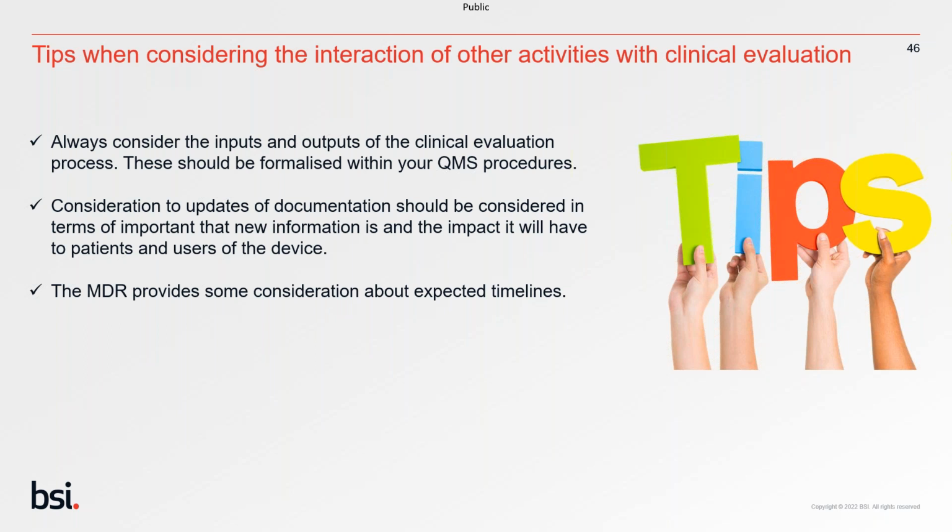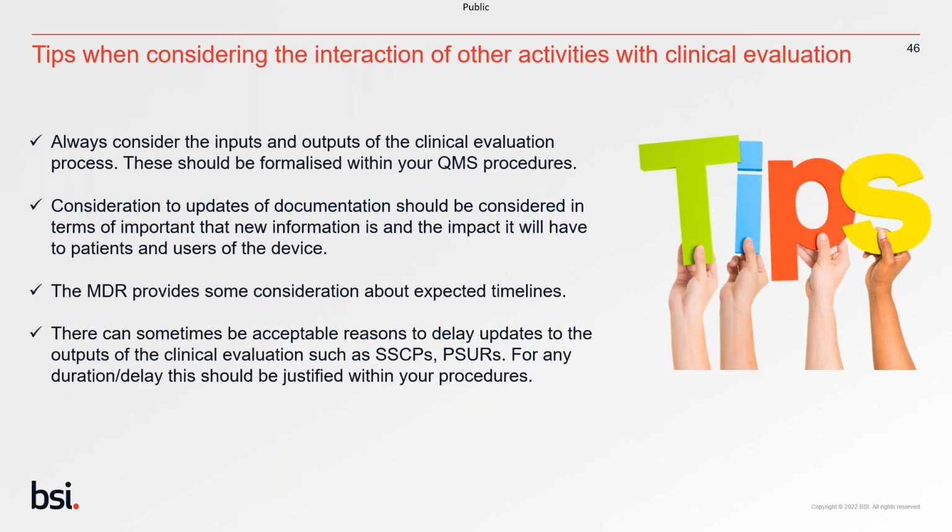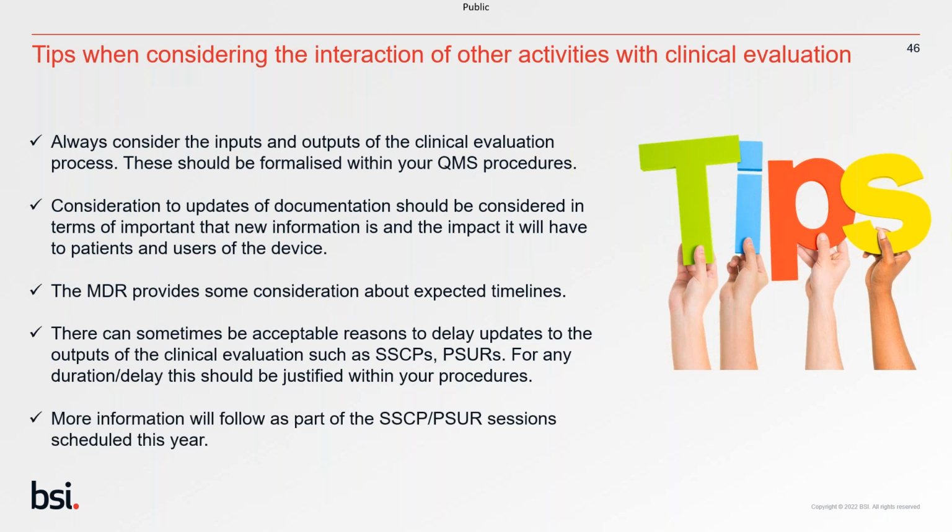The MDR does provide some consideration about what those expected timelines should be for each of those stages. There can sometimes be acceptable reasons to delay updates, such as updates to SSCP and PSURs, and these should be clearly documented within your procedures.